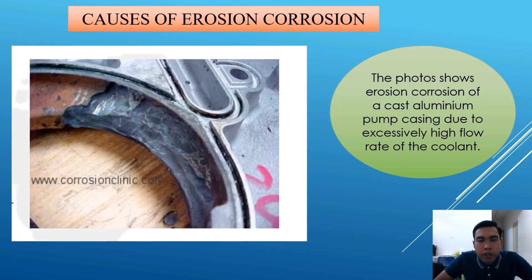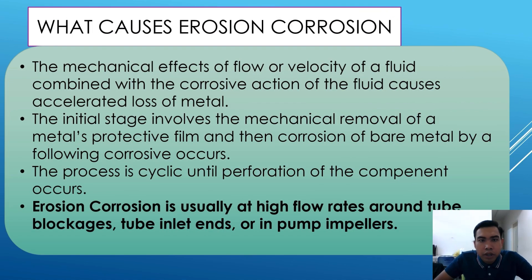Cause of erosion corrosion: the photo shows erosion corrosion of a cast aluminum pump casing due to an excessively high flow rate of coolant. The mechanical impact of flow or velocity of a fluid combined with the corrosive action of the fluid causes erosion corrosion. The initial stage involves the mechanical removal of the metal's protective film, then corrosion of the bare metal by the following corrosive flow. The process is cyclic until perforation of the component occurs. Erosion corrosion is usually found at high flow rates around tube blockages, tube inlet ends, or in pumps.